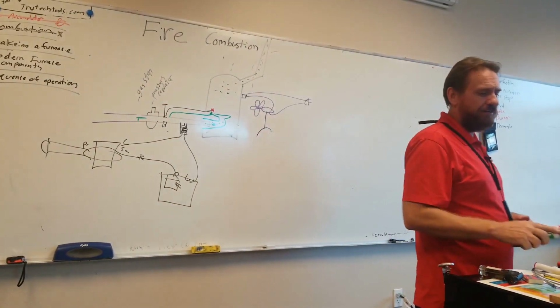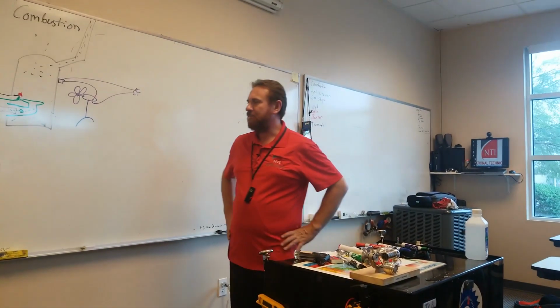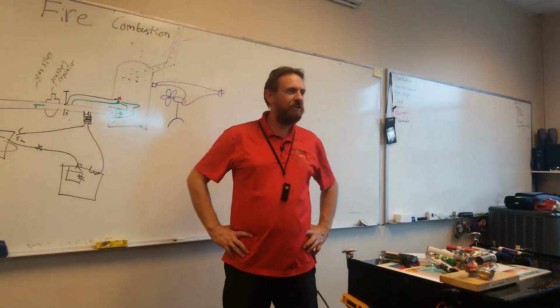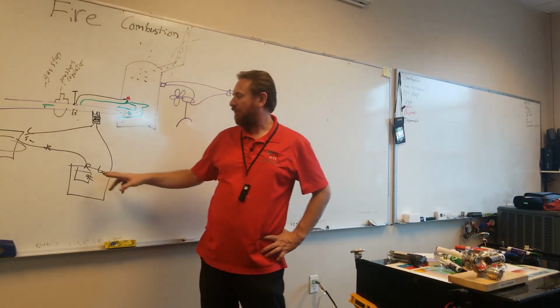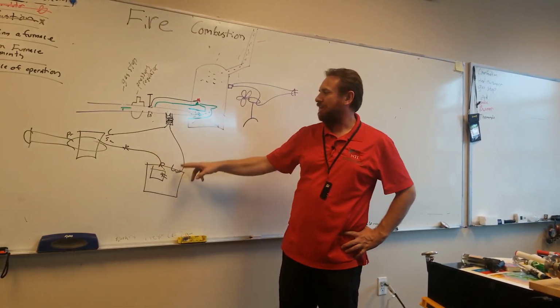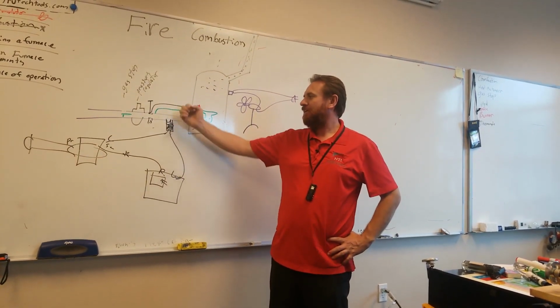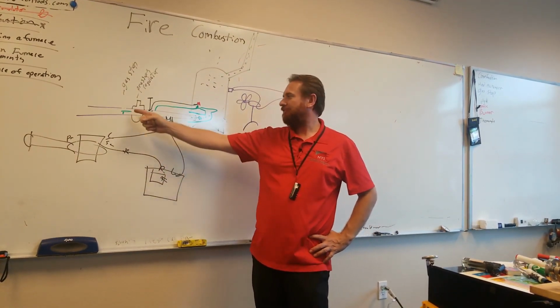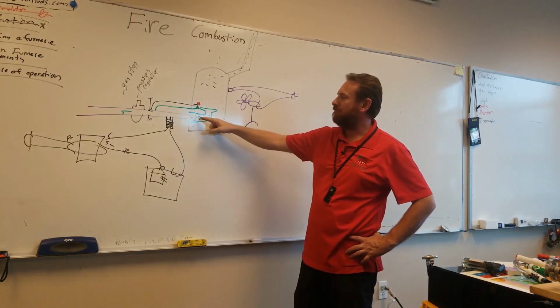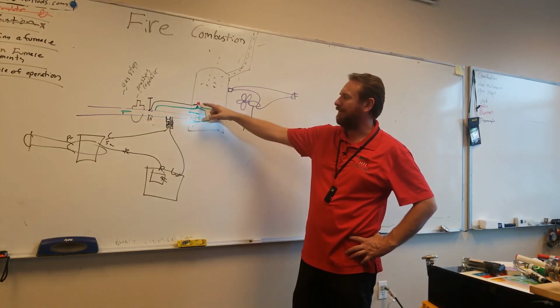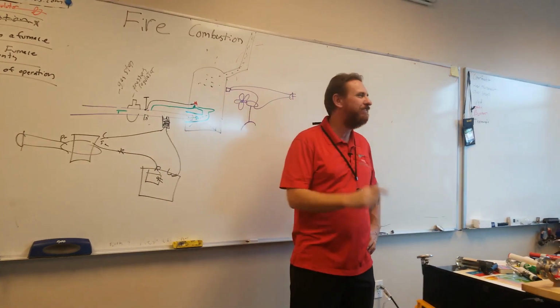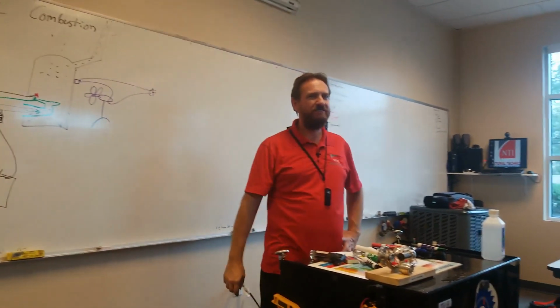So let's see if this would work. All right, so the temperature during the day or during the night cools down. Thermostat calls for heat, connects R and W. We energize my electromagnetic coil. That opens the valve. Gas flows through the manifold to the spud and orifice, mixed with primary air in the burner, across the pilot light, igniting into a flame that burns inside the heat exchanger.